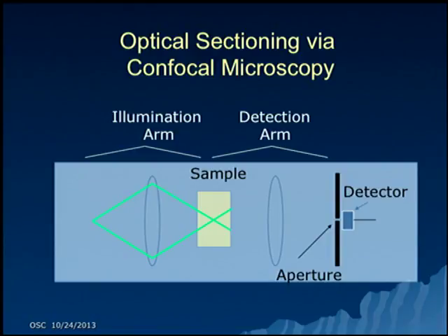So how does a confocal microscope work? There's a point source. It's imaged into a thick 3D sample at a certain location, and mostly what I'll be talking about today is fluorescence. If it fluoresces, there's a lot of light there, and the fluorescence from there gets imaged confocally onto a pinhole aperture. A lot of light gets through from that particular location. But what about other locations, like back here? It's in the illumination beam, so it is fluorescing, but when it images that fluorescence, it's blurred out.